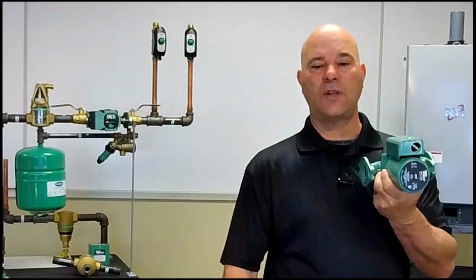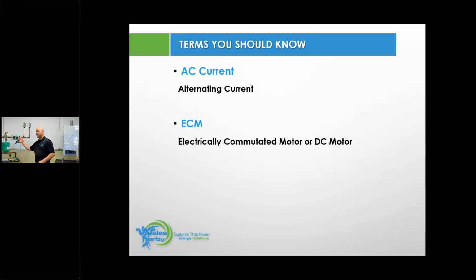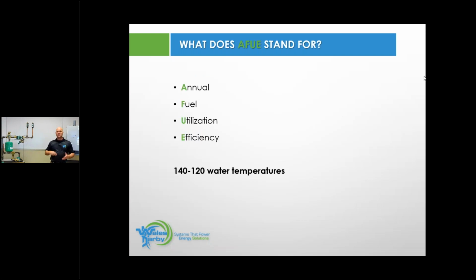And the reason for that is this is like running an 80-watt light bulb. 2,500 run hours in your typical heating season is how many hours a circulator runs. So by switching to an ECM, it will run the same amount of time, because that's how much run time we need to support the house. But this will run up to 85% more efficient than the standard 007 will, or the red one, or the purple one. If we're talking AC, it's like running an 80-watt light bulb. So just think of it that way. Here, we're running a 44-watt light bulb down to, let's say, a 10, 12-watt light bulb, depending on the demand. So just so you understand what's going on internally with these circulators.